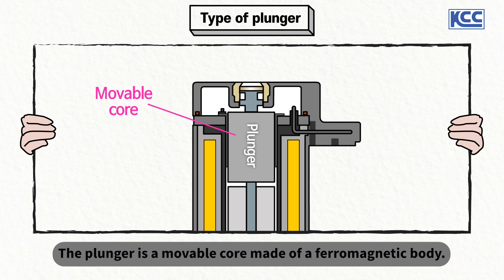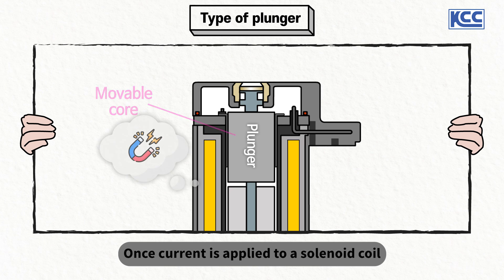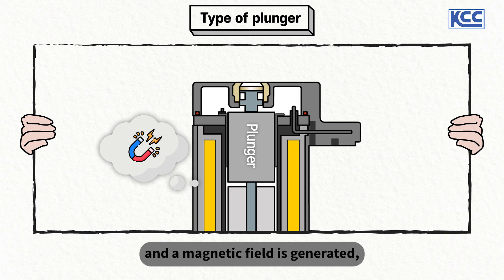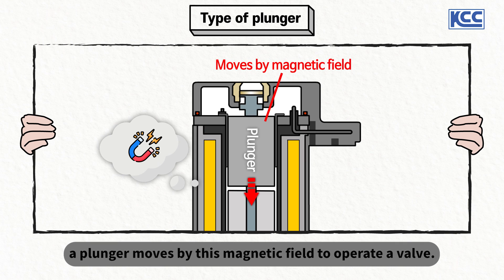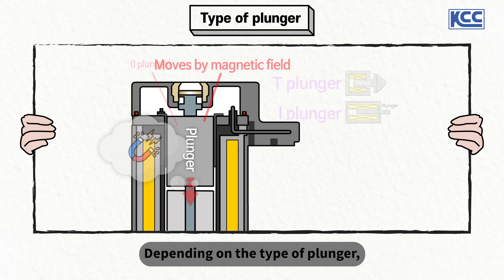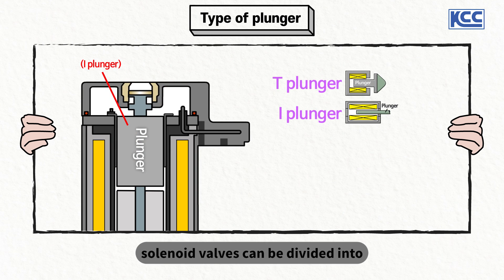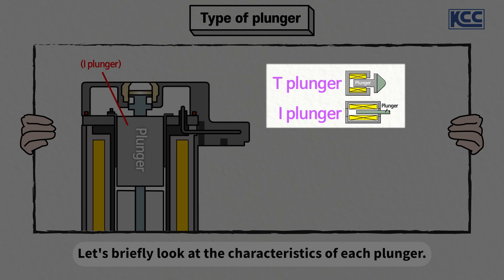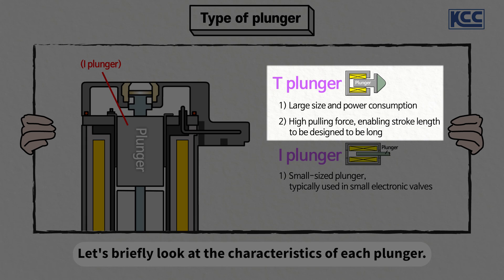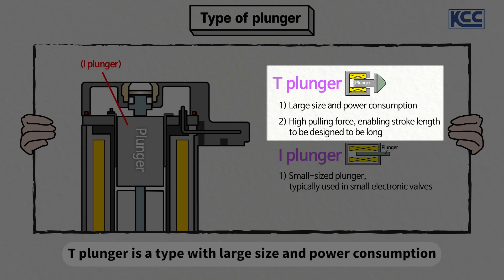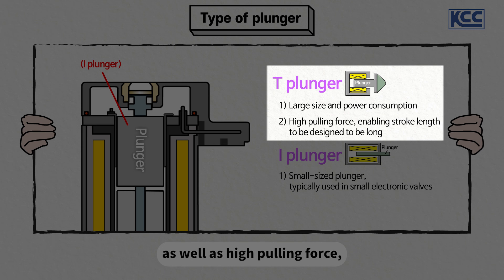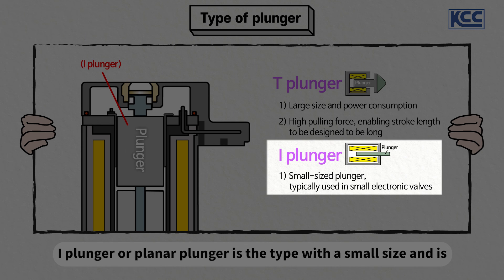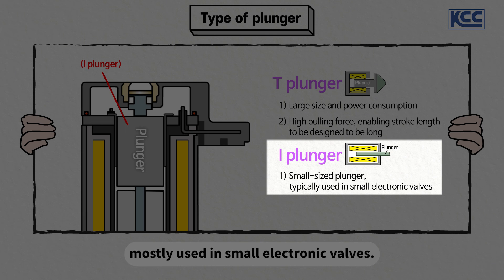The plunger is a movable core made of a ferromagnetic body. Once current is applied to a solenoid coil and a magnetic field is generated, a plunger moves by this magnetic field to operate a valve. Depending on the type of plunger, solenoid valves can be divided into the T plunger type and I plunger type. The T plunger is a type with large size and power consumption as well as high pulling force, so it is able to make the stroke length longer. The I plunger, or I plunger, is the type with a small size and is mostly used in small electronic valves.